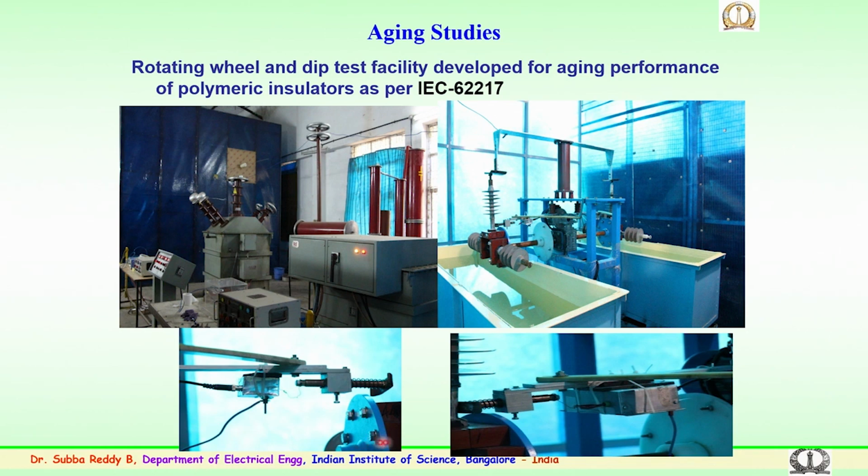So, this arrangement of 40 seconds dipping, 8 second transition and 40 second dripping, transition, contacting with the high voltage, then resting, everything is done using the proximity sensors which are placed on the white diaphragm which is shown here.